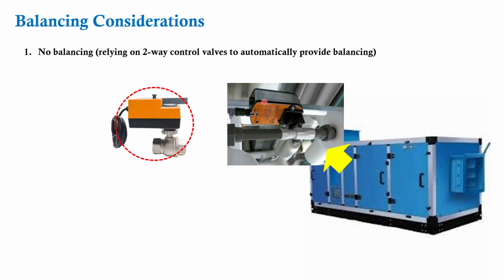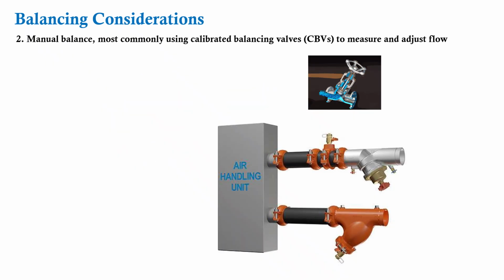So no balancing if it is only a two-way control valve. So there is an AHU, actually there's a coil, and in the coil, if only a two-way control valve has been provided, it's only going to regulate the flow between 0 to 100, but it's not going to balance it. So with respect to the temperature need and the flow requirements, it is not going to be able to control better, and how it is impacting I will show you in the subsequent part of the video.